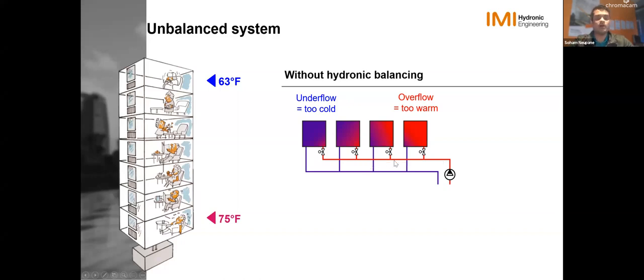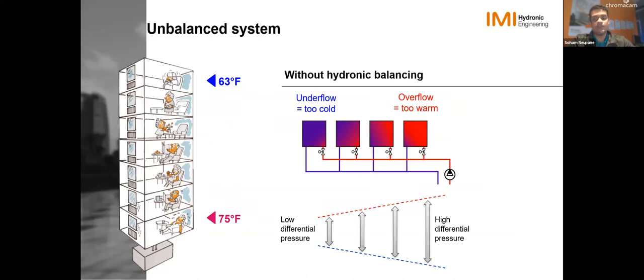And the farther you go, there are more pressure drops you have to overcome. And thus you're just going to have less and less water, and you'll start underflowing at a certain point downstream. And that exactly is what causes this temperature gradient in the building. People who live closer to the mechanical room are very hot and sweating, whereas people living up top are probably freezing. So that's something we see commonly when a system's not properly balanced. And that's because you do not have a good differential pressure distribution. You have high differential pressure closer to the pump, you overflow the circuits, move further, lower DP, you underflow the circuits. So some rooms are too hot, some rooms are too cold, and control valves just cannot solve this issue. You do need balancing valves to be able to not overflow your system and balance it.